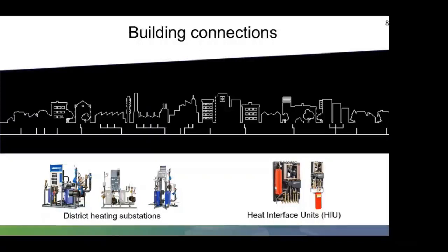There are also many different options for building connections to a district heat and location of the substation or heat interface units. This all depends on who will own and maintain the substation or the heat interface unit. It could be the building owner, the energy company, or the end user, but no matter what, the energy efficiency is always the key. Today, we're going to focus on substations, whether it's connected and located at the building with a single connection or the heat source feeding multiple buildings. Some of the key criteria must be considered, and the same core principles for the design need to be carefully considered, given the high energy efficiency and the greater solution they give us.